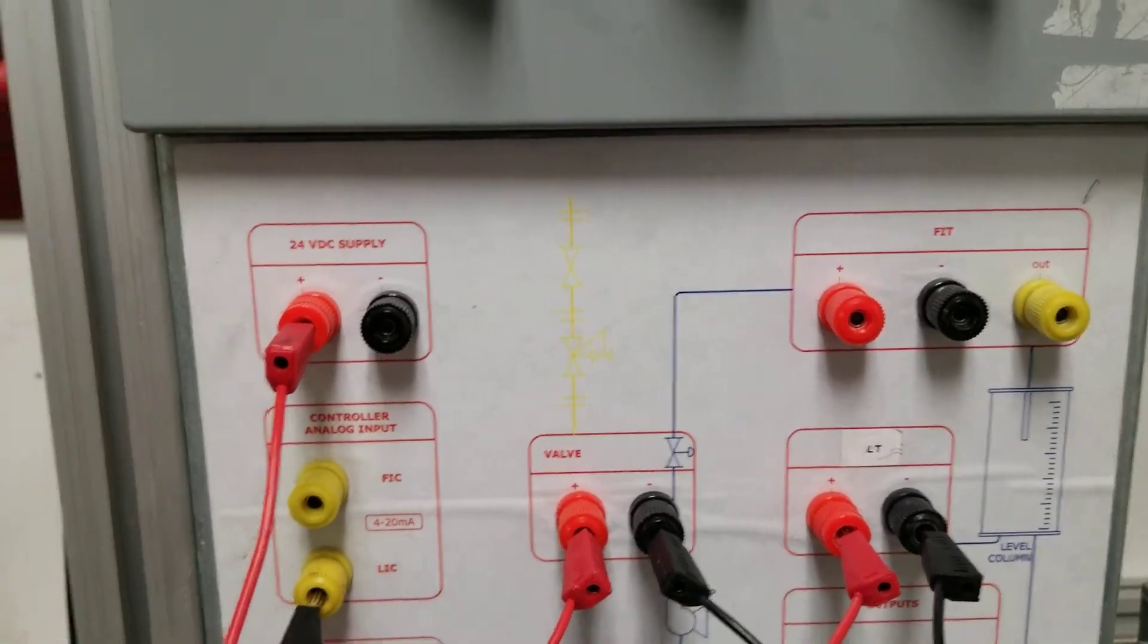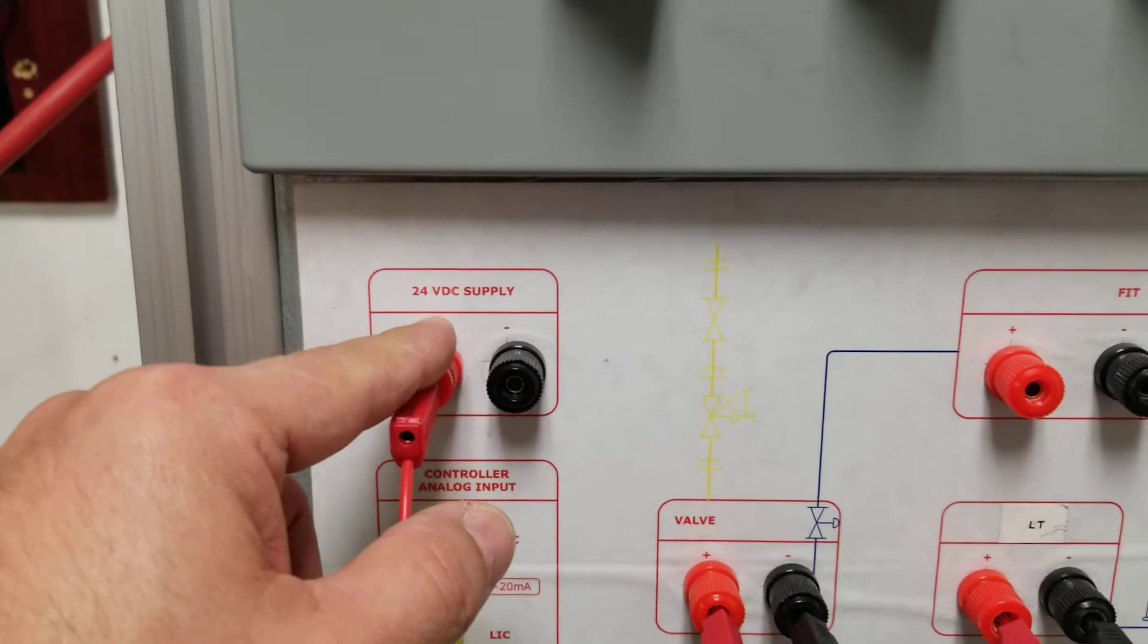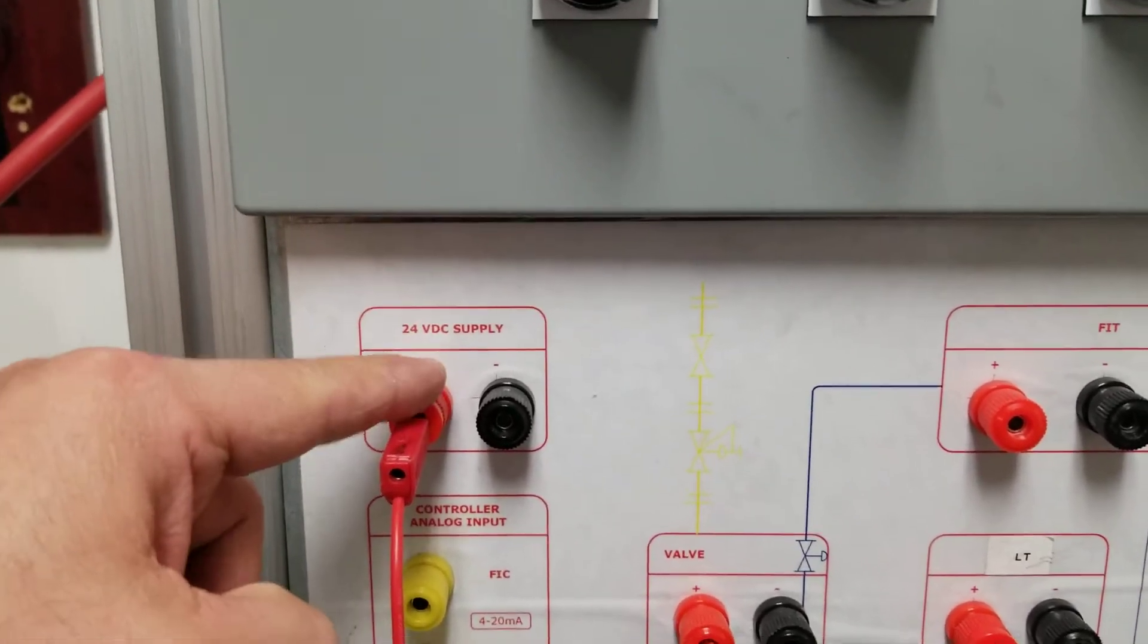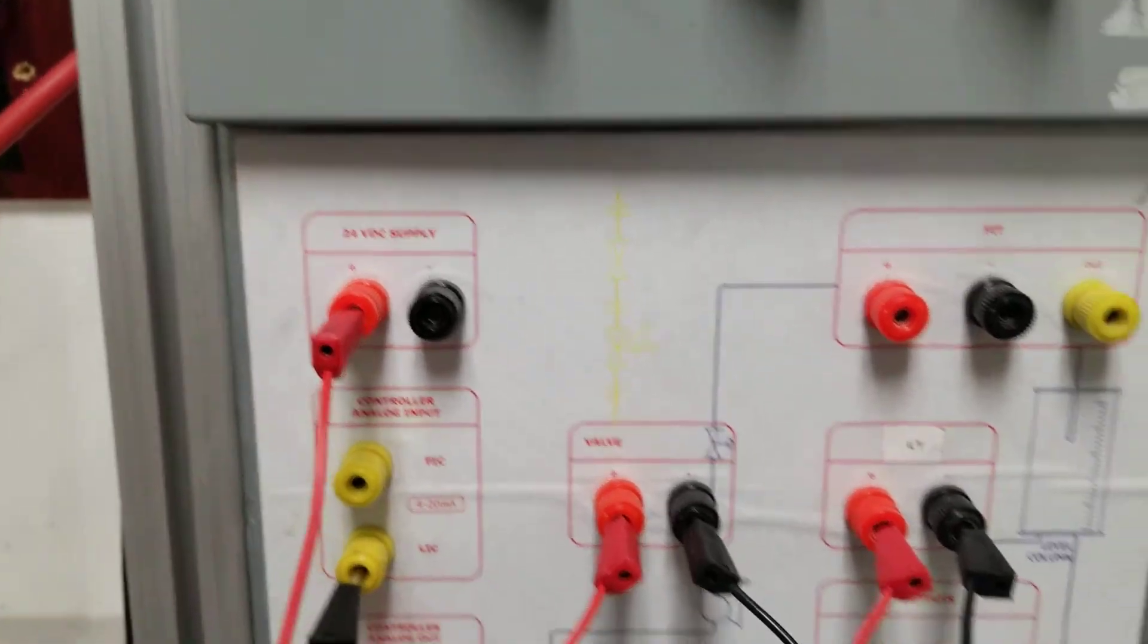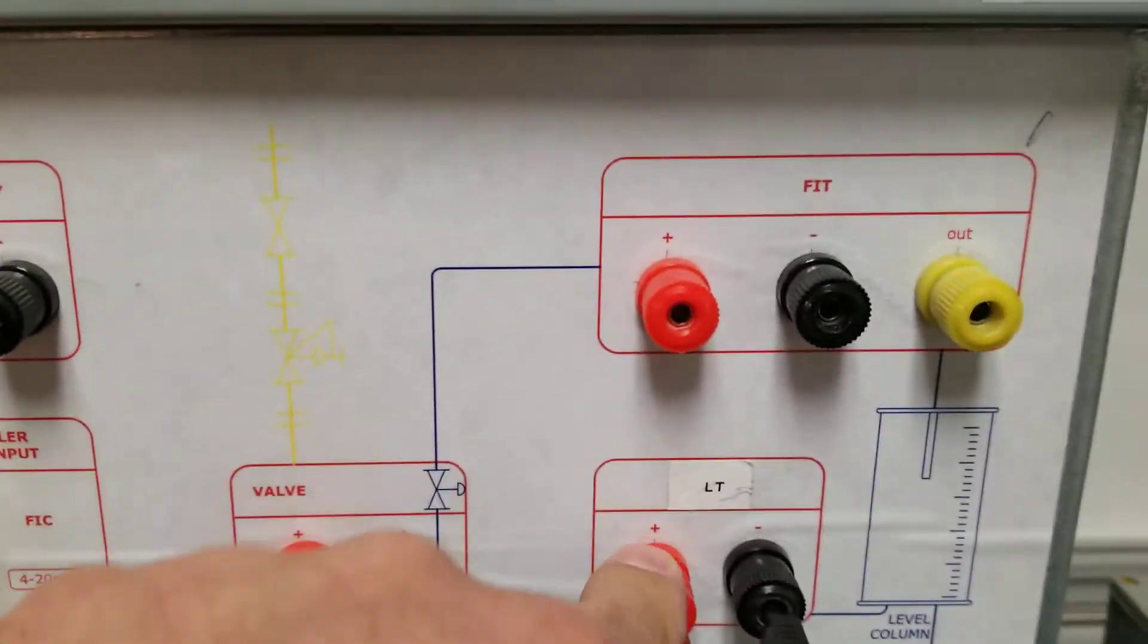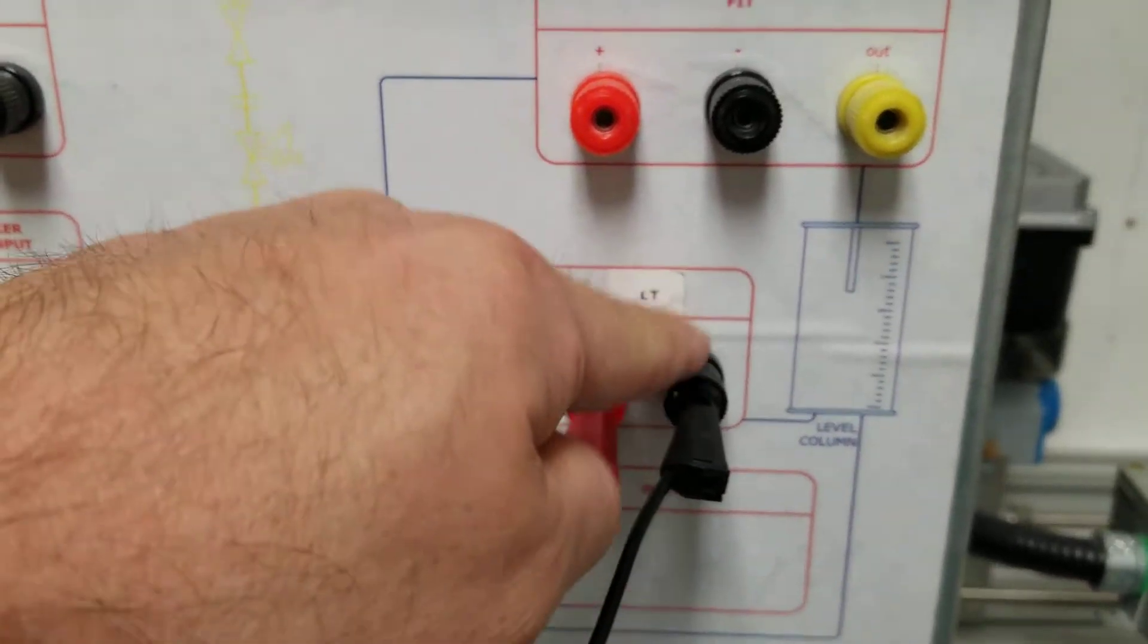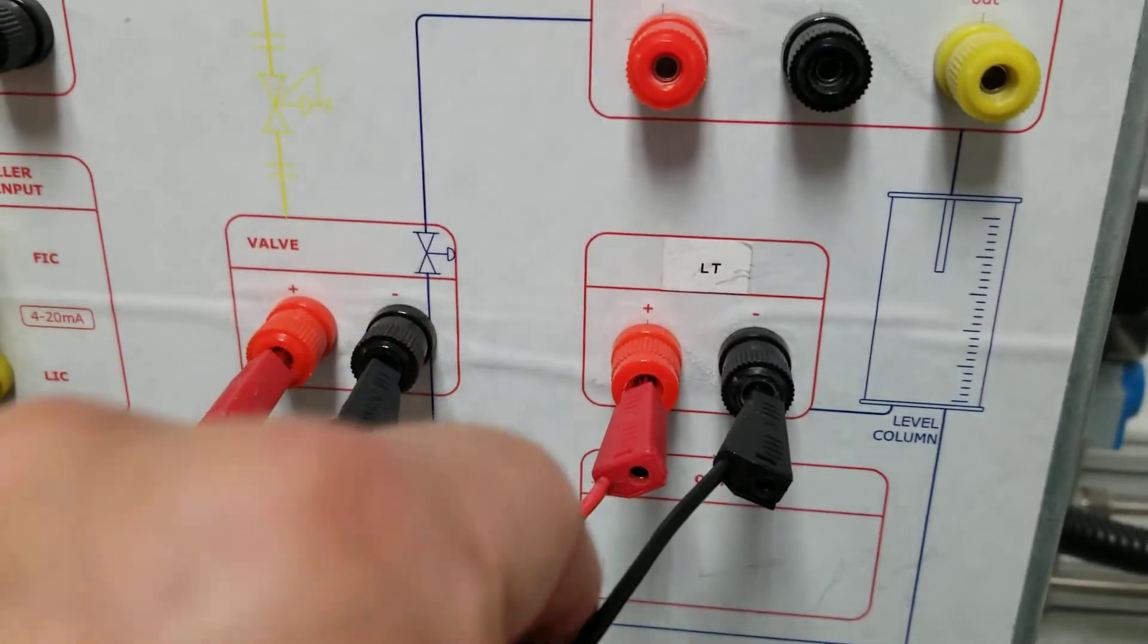Here you have a 24-volt power supply; we only need to use the red or positive. We're going to send a positive to LT, which is the level transmitter. From the level transmitter, the output is going to send a signal to the level indicator controller.